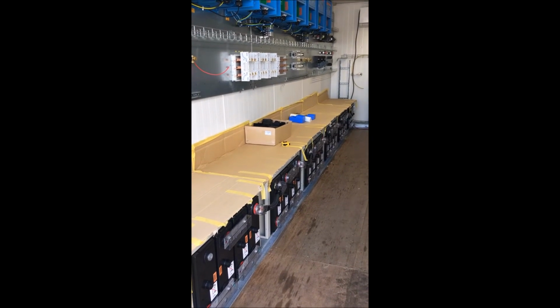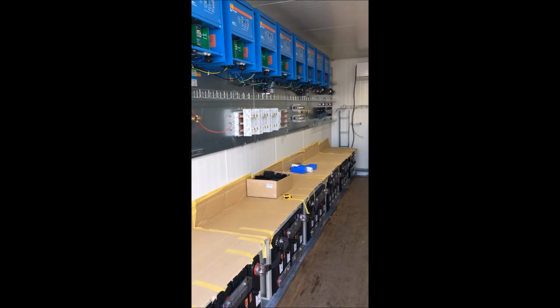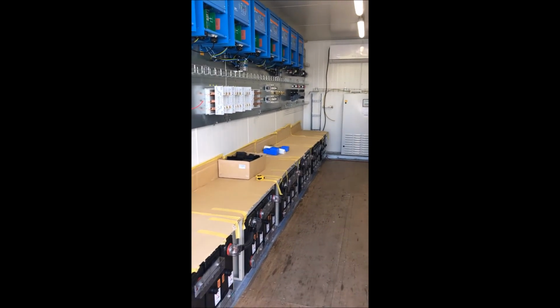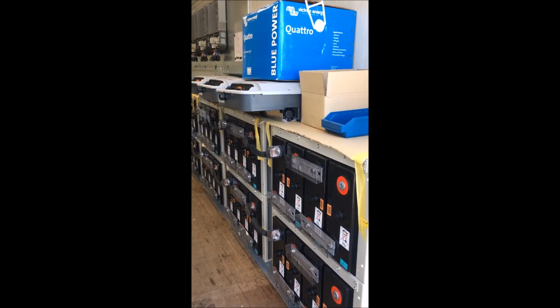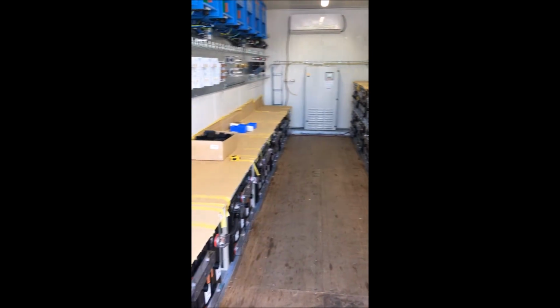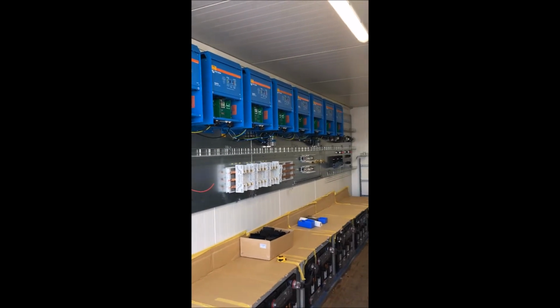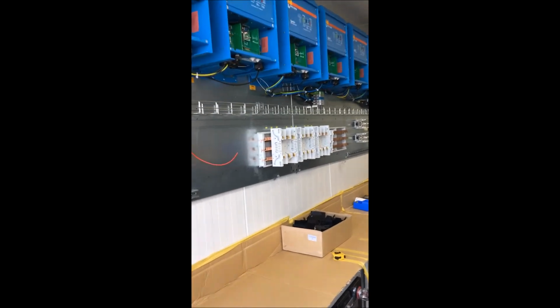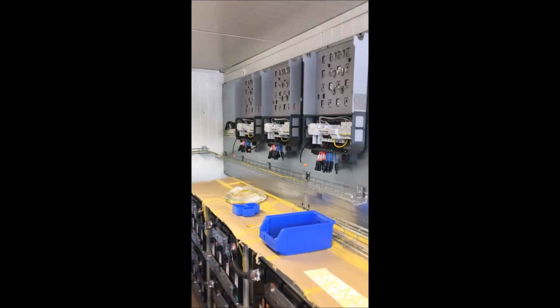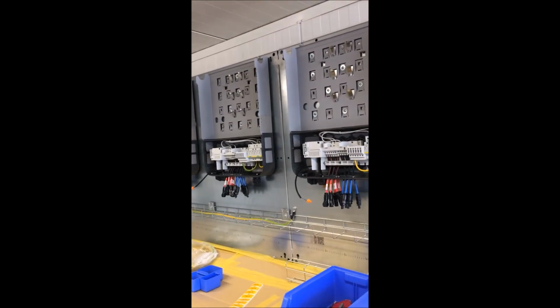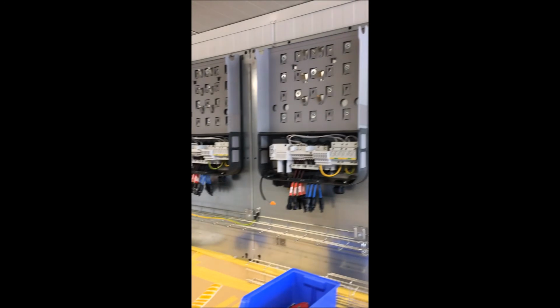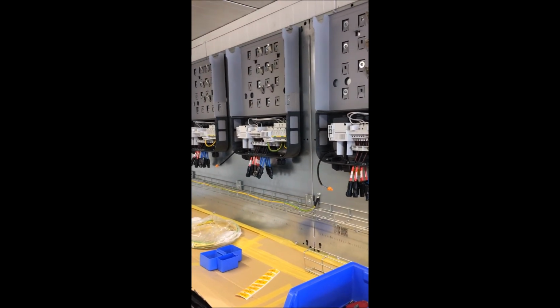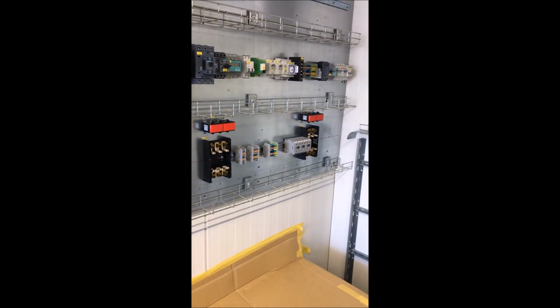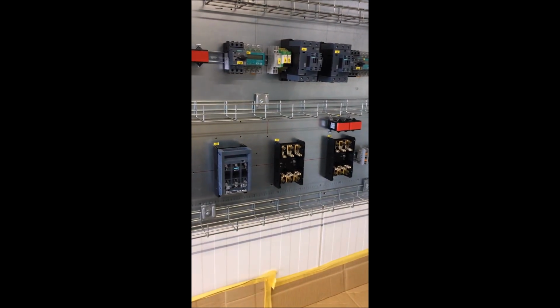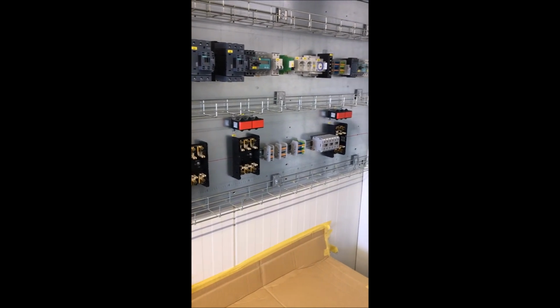In this picture we show you the production of a battery system which has 150 kilowatt hours net, which can be taken out from the batteries within 8 hours, and a total of 90 kVA of inverter power. And in this cabinet we install the solar inverters on the right side. Here we have now 3 inverters, but there's actually space for 4 inverters to be installed. Maximum capacity of each inverter could be 27 kilowatt. Based on client's request, we can of course also incorporate an AC switchboard with multiple outlets according to whatever the customer's needs are.